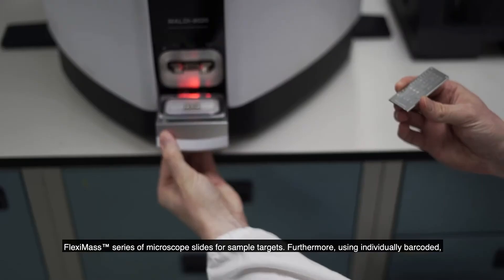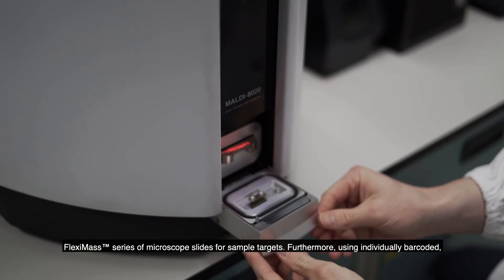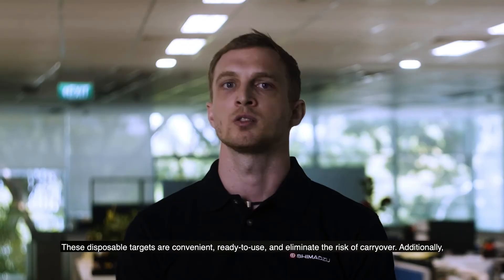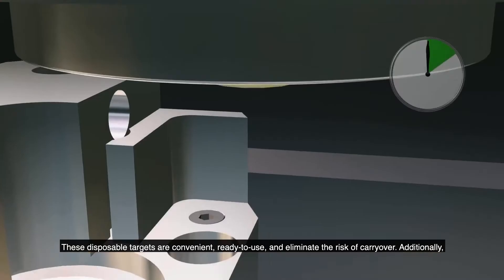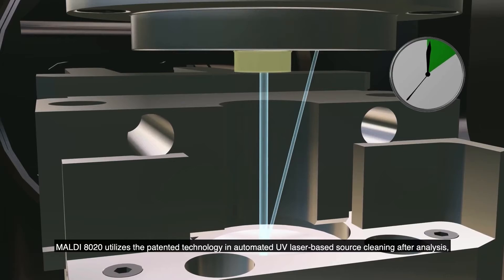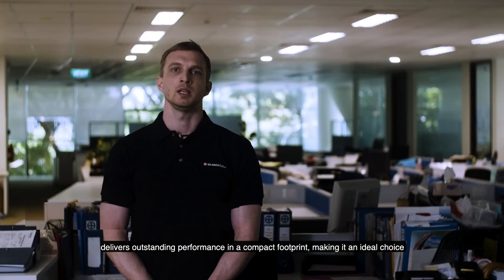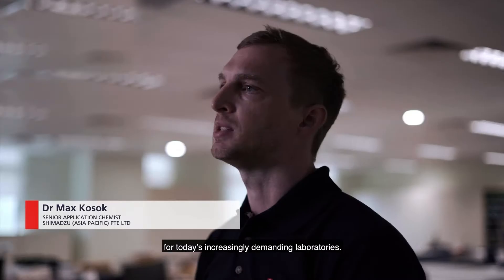Featuring our MALDI 8020, a benchtop linear MALDI-TOF mass spectrometer, its strengths lie in its load-lock chamber for fast sample introduction and its compatibility with the FlexiMass series of microscope slides as sample targets. Using individually barcoded single-use FlexiMass DS slides provides a suitable solution for routine or defined workflows. These disposable targets are convenient, ready to use, and eliminate the risk of carryover. Additionally, the MALDI 8020 utilizes a patented technology for automated UV laser-based source cleaning after analysis, cleaning the extraction electrode in situ without breaking the instrument vacuum. The MALDI 8020 delivers outstanding performance in a compact footprint, making it an ideal choice for today's increasingly demanding laboratories.